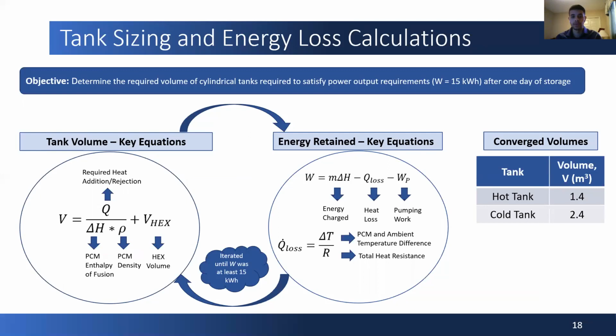For tank sizing, we first had to consider the fact that our system needs to store energy for a total of 24 hours. As larger tanks result in more heat loss, we had to go through an iterative approach in order to get a converged value of 15 kilowatt hours after storing energy for a whole day. The final tank volumes were 1.4 meters cubed for the hot tank and 2.4 meters cubed for the cold tank.